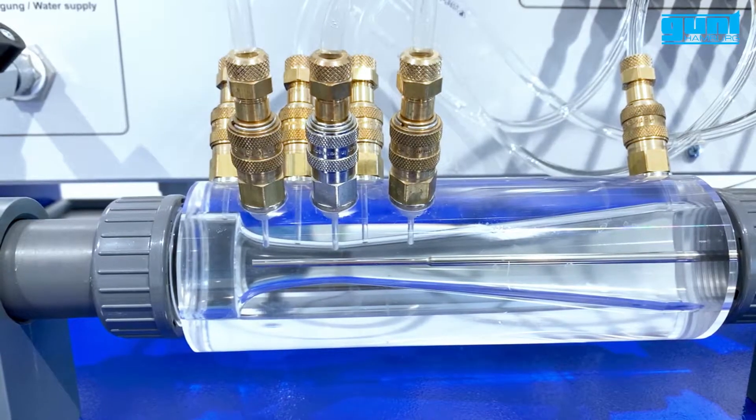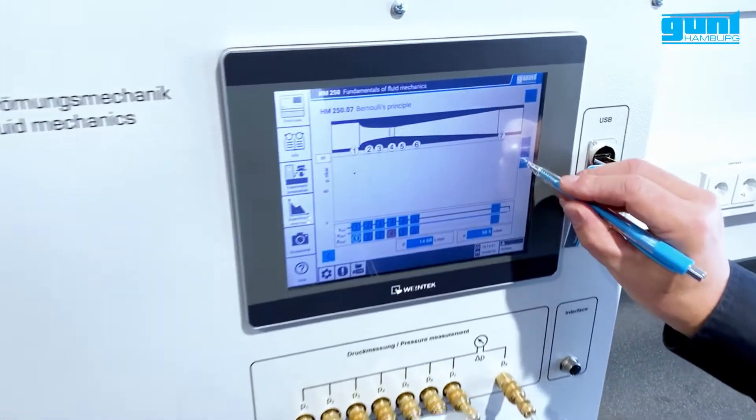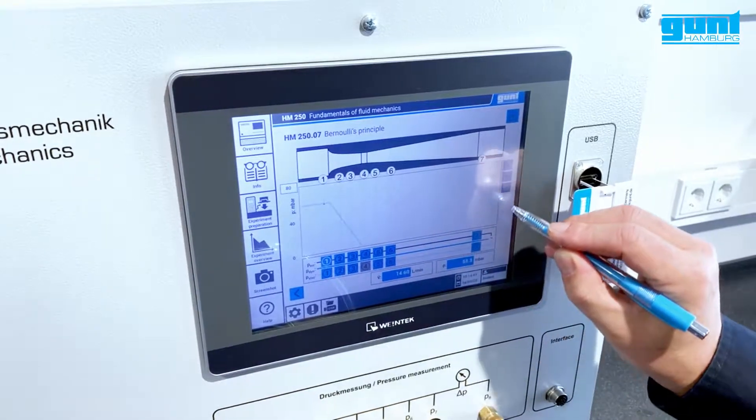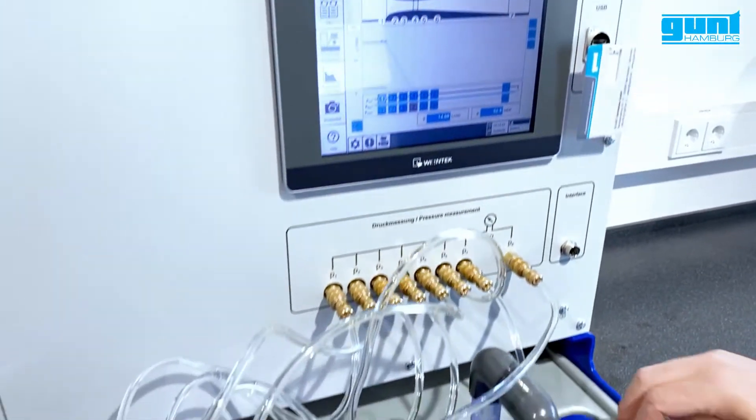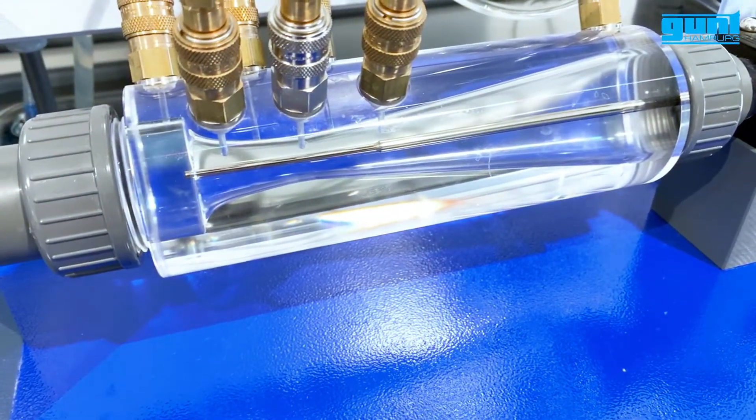After we have positioned the pitot tube at the respective location, we activate the location in the Overview and press the plus button to record the measurement. We do this for the static pressure and the total pressure.